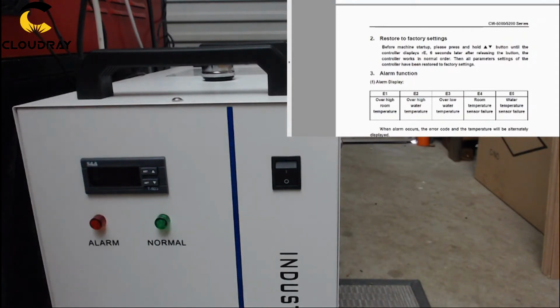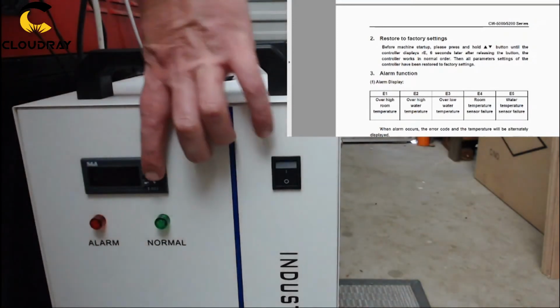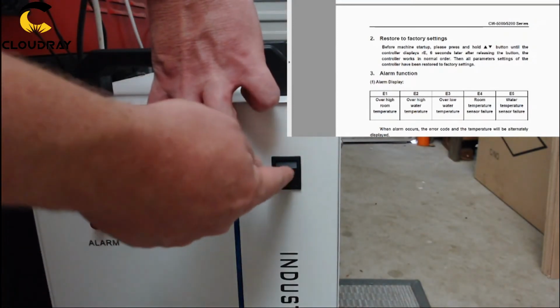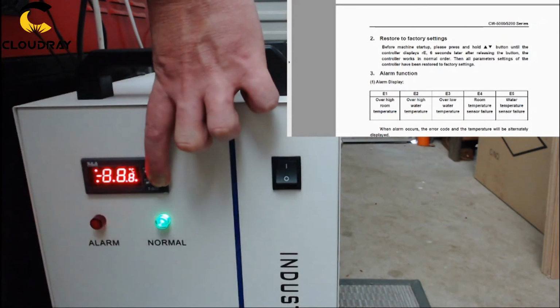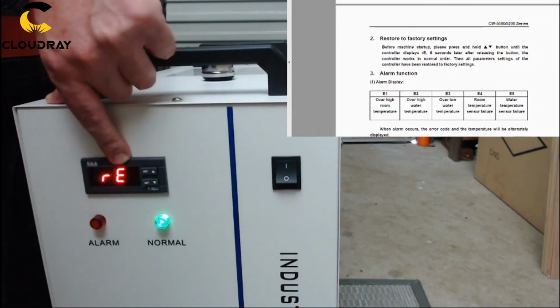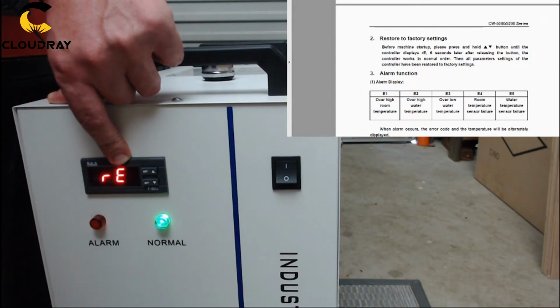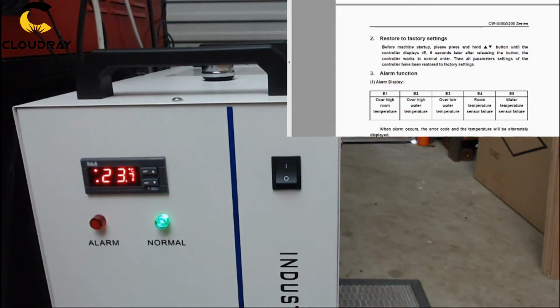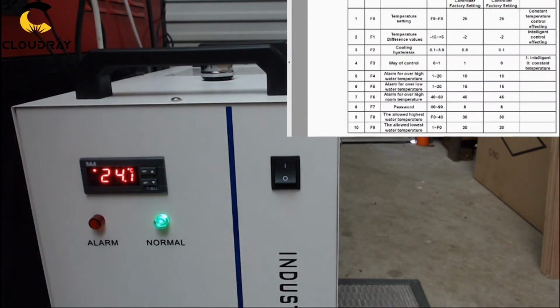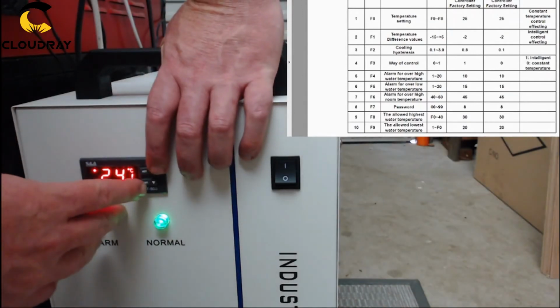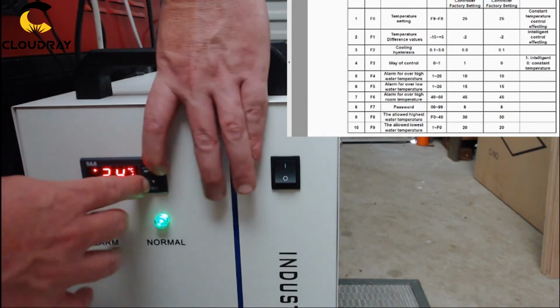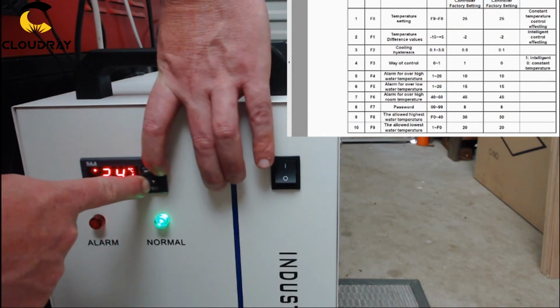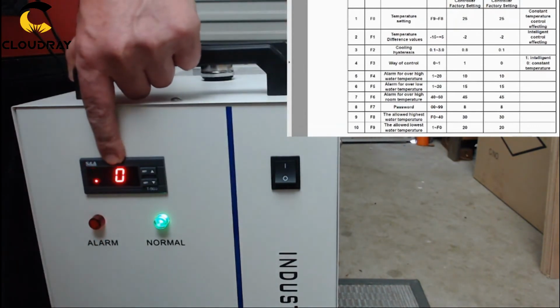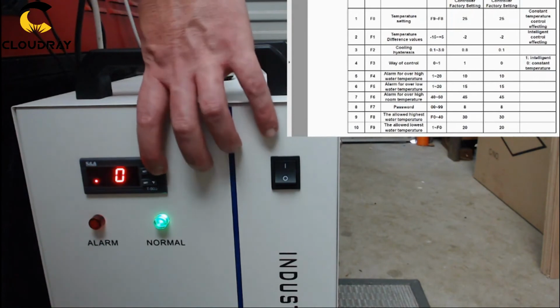So firstly, to do a factory reset, we need the machine off. We press and hold both the up and the down buttons, hold those in, and then power on the machine. This RE means that it has been factory reset. The next thing we need to do is get into the thermostat parameters. So to do that, we need to press the up button and the set button together and hold. This 0 is asking for the password. The default password is 8.